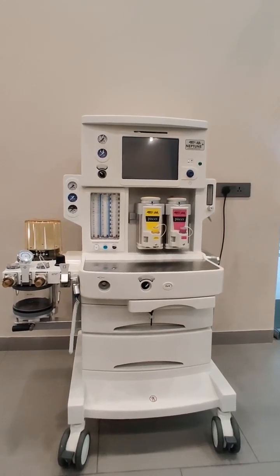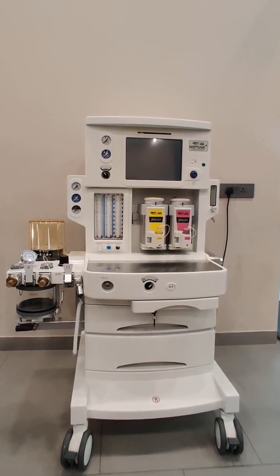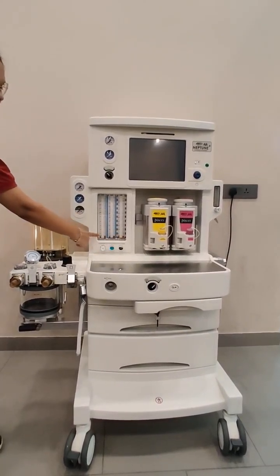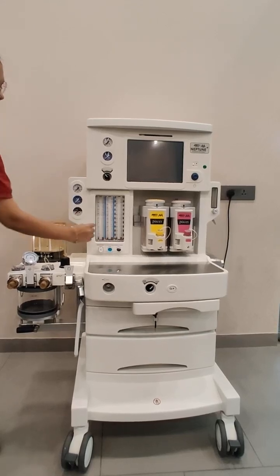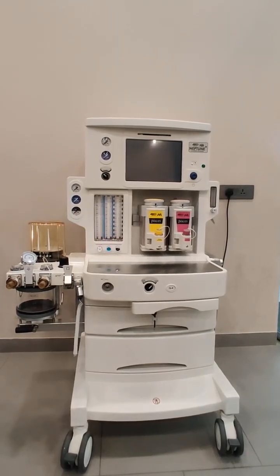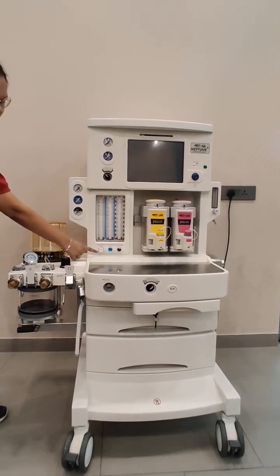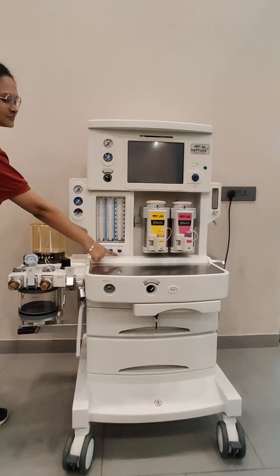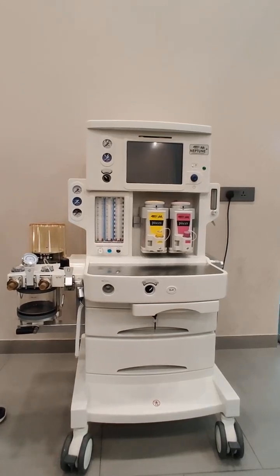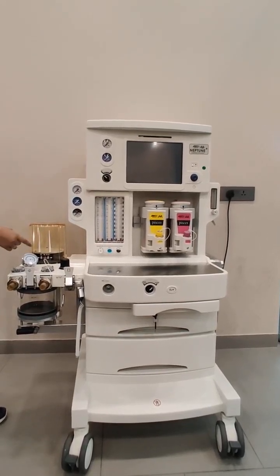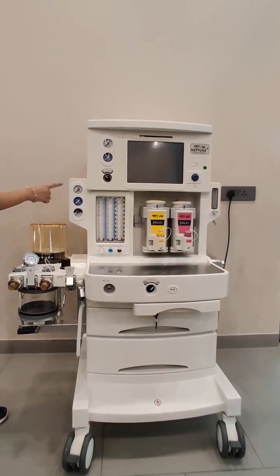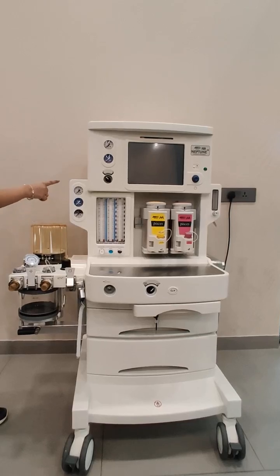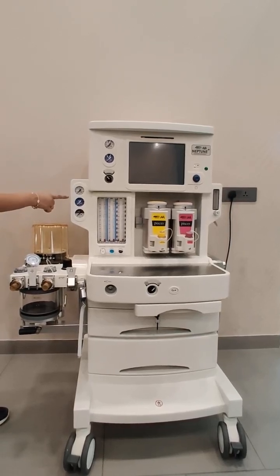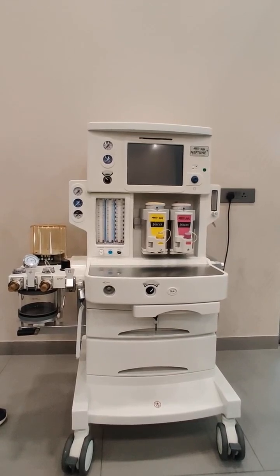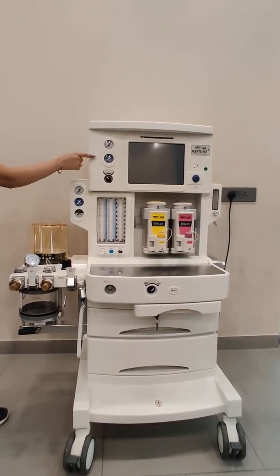This machine comes with the 3 gas configuration. So we have the 6 tube rotameters, 2 for oxygen, 2 for nitrous oxide, and 2 for air. We have dedicated knobs for each and every gas: the oxygen knob, nitrous oxide and air. These are color coded as well as touch coded. Then we have the input pressure gauges. These 3 gauges are for the pipeline system. So for the input we are giving pressure gauges to depict the pressure, and for the cylinders we have one pressure gauge for each yoke.